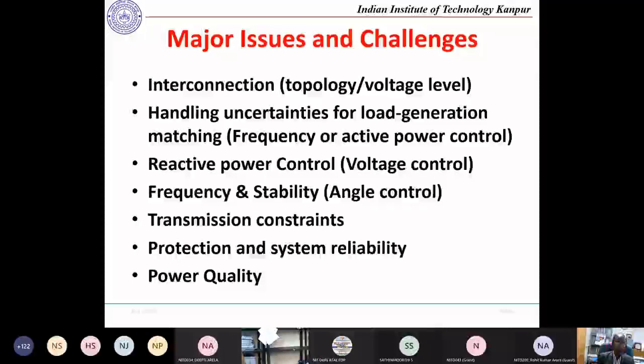These renewable devices are designed and rated mainly for active power output. During peak hours they give maximum power, so current flows fully through the power electronics devices. But during off-peak times, there's margin available, so reactive current can flow through these thyristors or power electronics devices to help control voltage. Especially at night, PV is almost idle, so why not use the same device to control reactive power during night time? People are trying to utilize this.